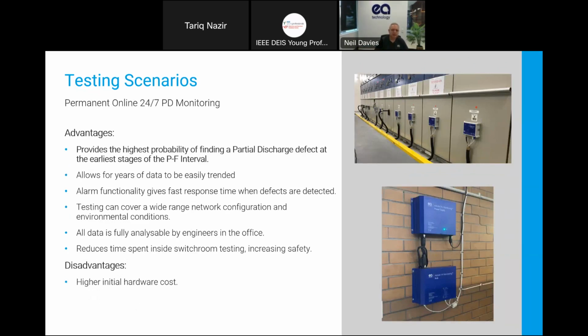And then you get to the ultimate. There's a big trend in the industry towards permanent monitoring of condition monitoring, partial discharge, and other techniques, basically. And this is great in the fact that it provides you the highest probability of finding the partial discharge defect at the earliest stage. So you can see when it started. I mean, if you put a monitor on and you've already got PD there, you don't know when it started, but you're looking forward. So it allows for years of data to be easily trended. It gives you fast response time. So if something happens, you can be warned very, very quickly. And of course, you've got all the network configurations, environmental conditions, and everything else.